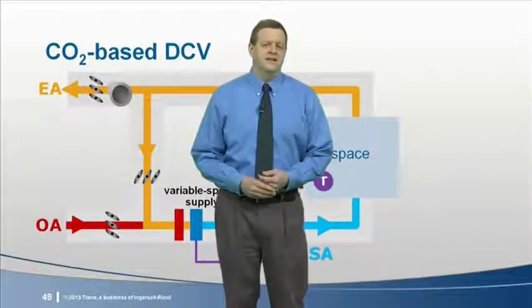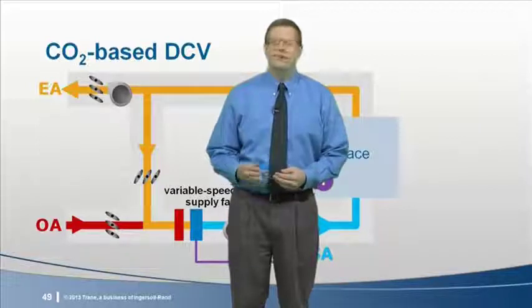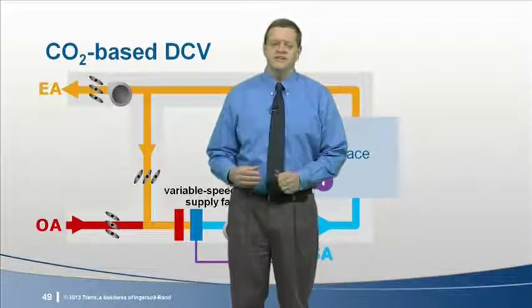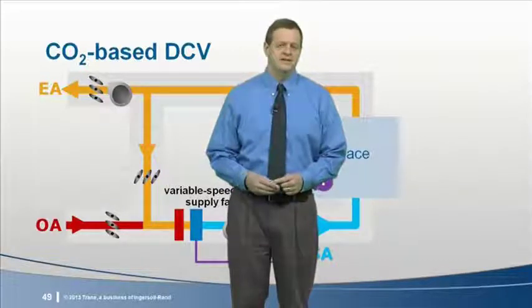Because the supply fan speed changes, ensuring proper ventilation in a single-zone VAV system is probably more challenging than for a traditional constant volume system. So be sure to give it more consideration when designing the system and its control. These strategies John mentioned are a good start. Before leaving the subject of ventilation, single-zone VAV systems are often used for densely occupied zones with varying population. This typically makes them good candidates for using CO2-based demand control ventilation. Carbon dioxide is produced by the occupants and diluted by outdoor air. So the difference between indoor and outdoor CO2 levels can be used as an indicator of the outdoor airflow rate being delivered to the zone.